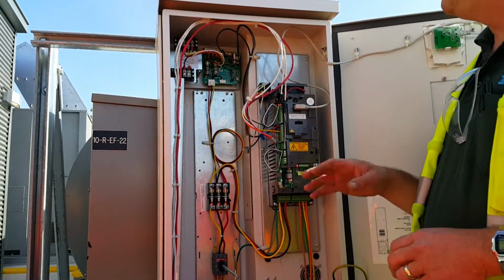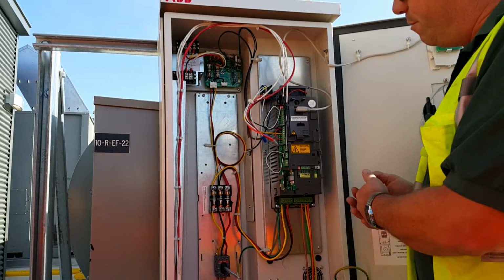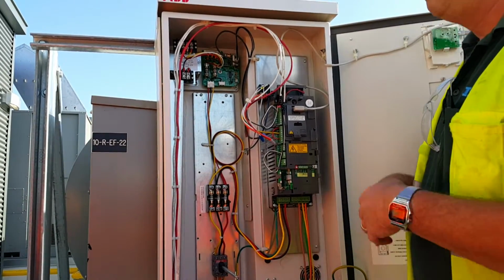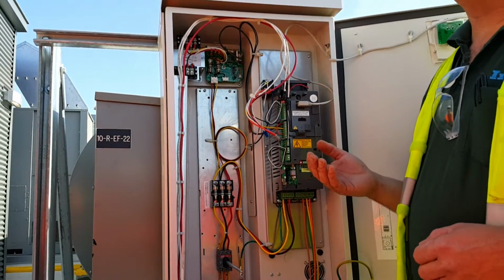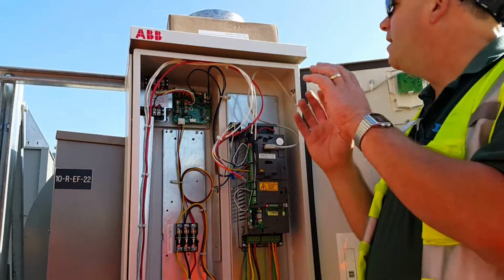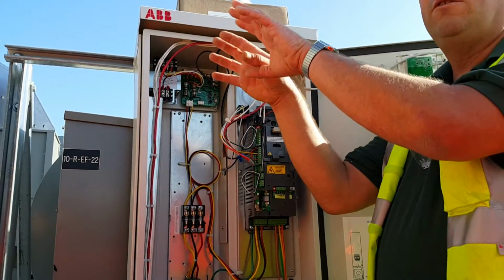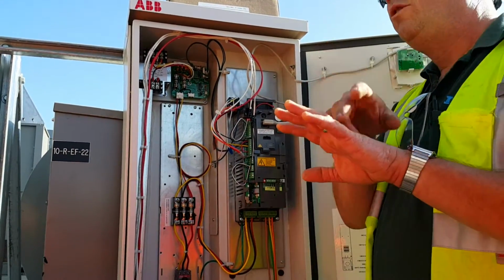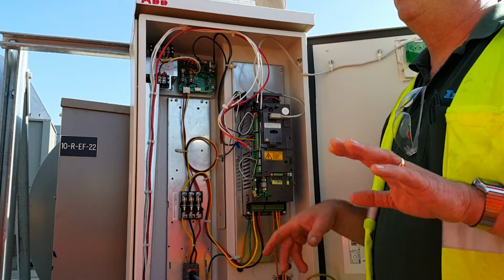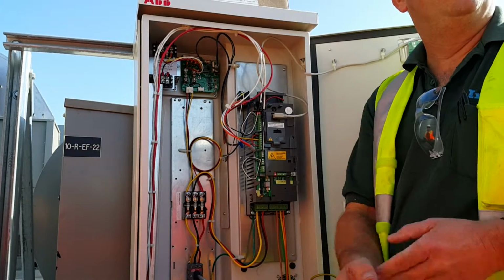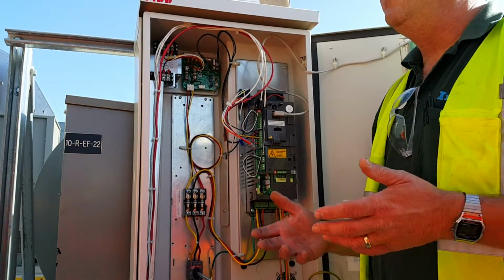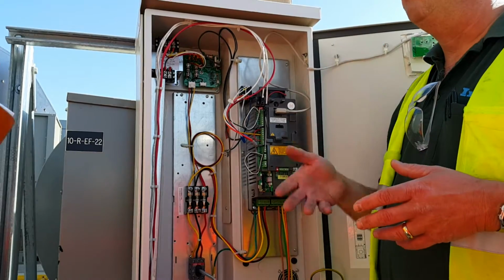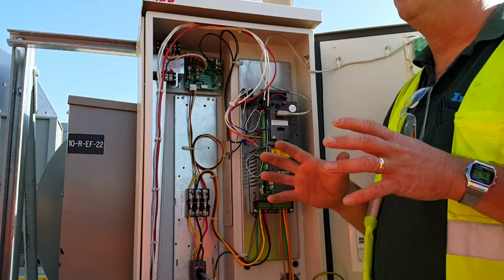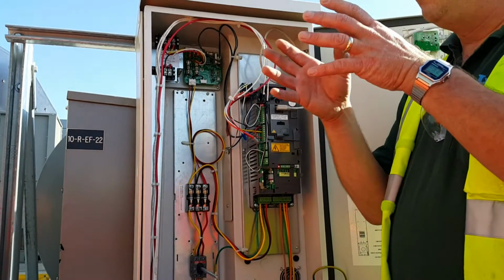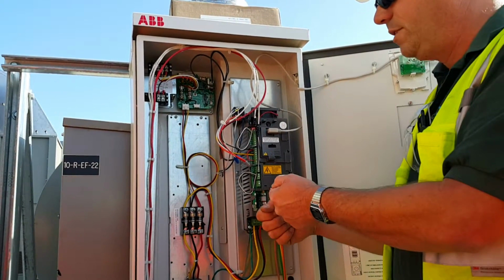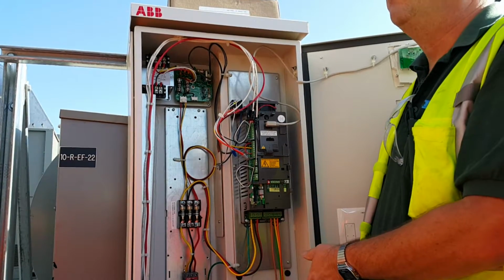Other good troubleshooting too, let's say I removed it, it was coming up with an earth fault as soon as I tried to start, or an overcurrent, and I remove the motor and I don't have that. The next good troubleshooting tool, a little harder here because it's sitting out here, but like the ones over here in the pumps, where we've got 3 of them next to each other, you can wire that drive to the other motor. If it runs that motor, you've got your good drive. It's just a simple process of elimination you would normally do in mechanical stuff, but because of the drive, people miss it just because they get overwhelmed because it's a high-tech piece of equipment. So you can take one of the drives and just get some wires, bring it over to the other motor, and run that motor. If it runs that motor, fine.